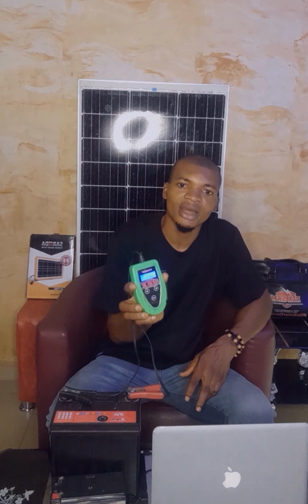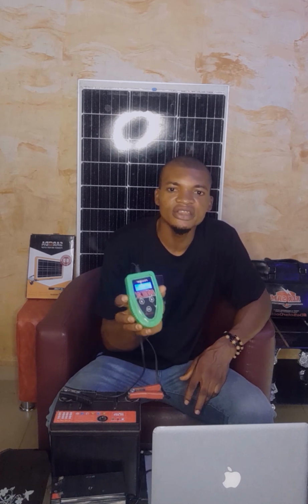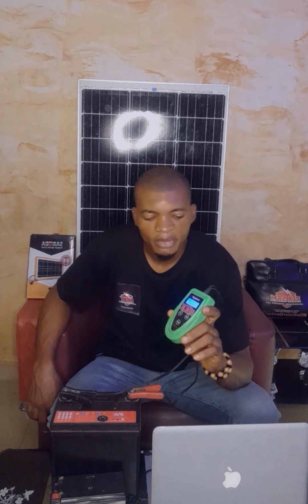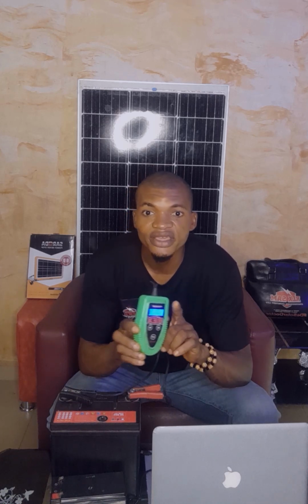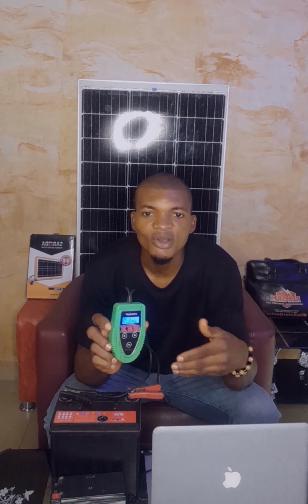If the internal resistance is too high, no matter how many hours you keep the battery to be recharged, it will never handle any load after charging. Why? Because the internal resistance will not allow current to be stored in the battery anymore, because the internal resistance has gone too high. Remember, this is measured in milli, not even in ohms, it's in milliohms. So the moment it increases and keeps on increasing, the cycle will keep on going down. That is how it works.